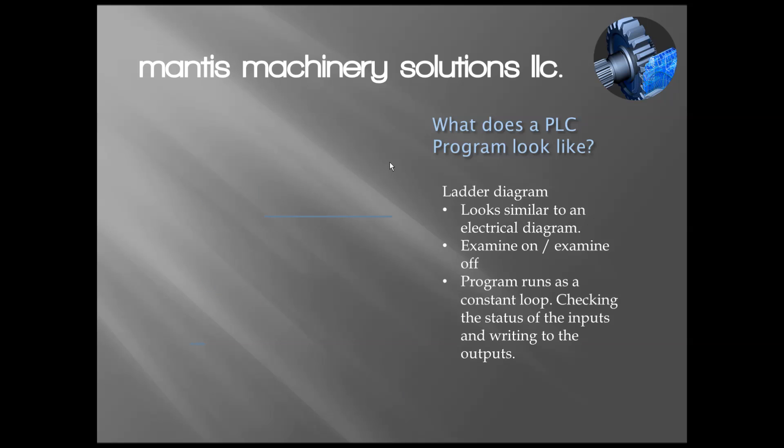Let's talk about how that software works. The program is done in what's called ladder logic. You can see this here looks a little bit like a ladder. I've got a left side and a right side and then I have these rungs. The reason it was originally drawn like this is because it looks very similar to an electrical diagram. On the left hand side, imagine I have my input power, my hot. On the right hand side, imagine I have common.